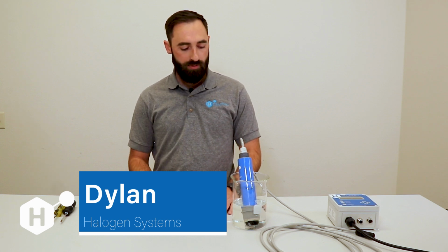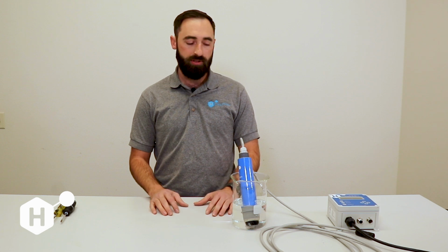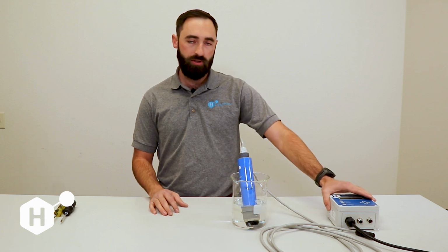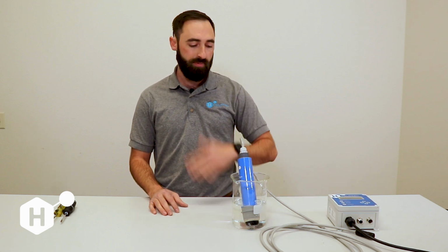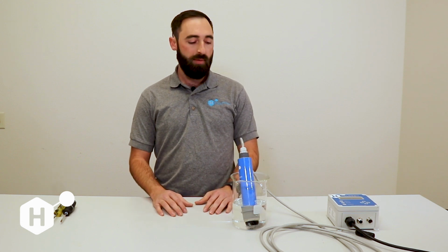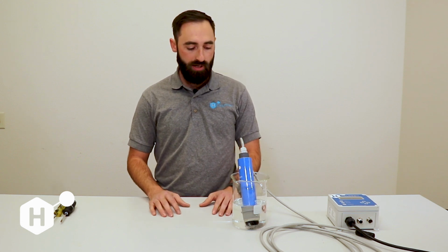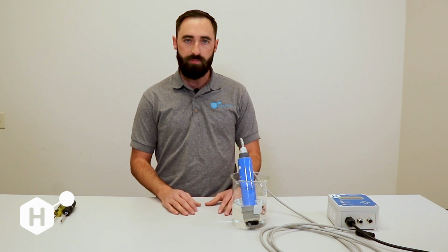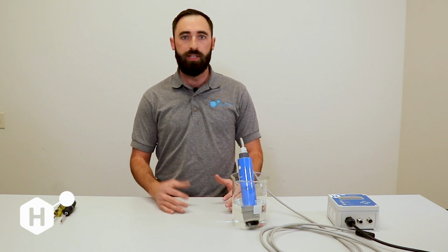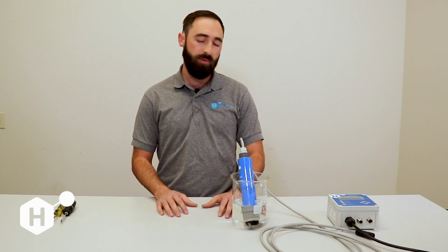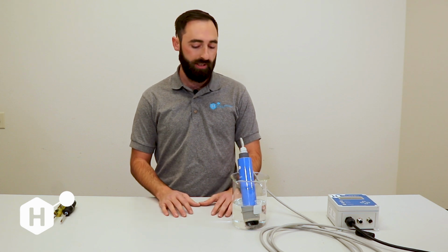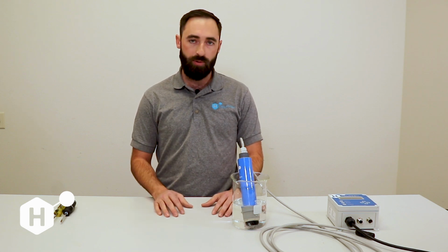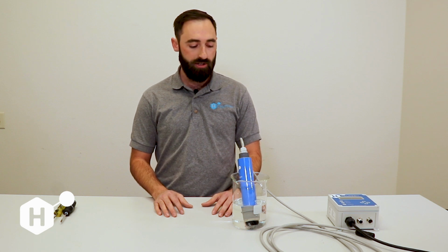This is our municipal low flange side stream sensor and one of our CN01 controllers. However, this procedure can be done with any sensor. Basically, we're going to go through how to get familiar with our system and make sure everything's working well before installation into whatever process you're using. So this will work for ballast water systems, municipal drinking water systems, wastewater systems, and cooling towers. This is something to do to really get familiar with your product prior to installing it into your system.